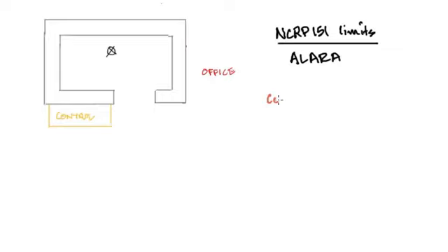So first we're going to consider a controlled area, like the control console. That's an area where you've got radiation workers, people with badges, where the area is controlled. NCRP 151 says in this area we should shield so that we get less than 1/10 of the maximum permissible dose. That's what they mean by as low as reasonably achievable. That's how they define it for this controlled area.